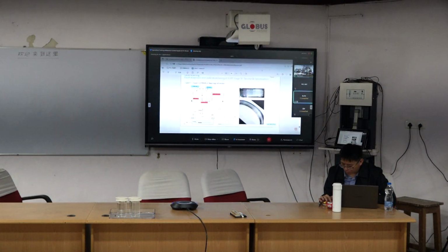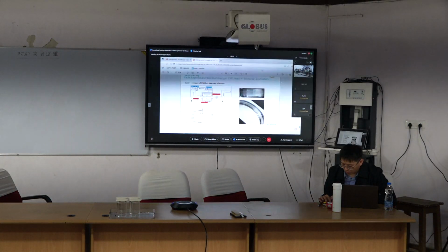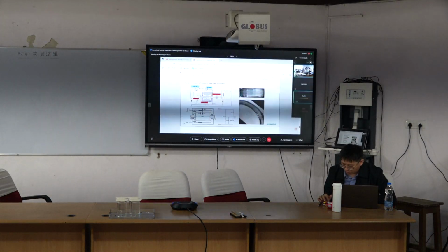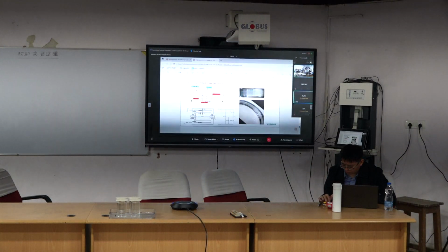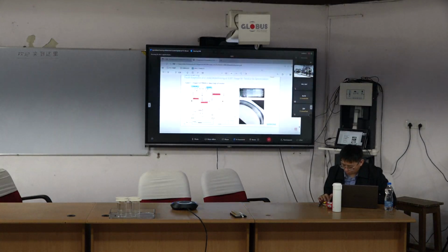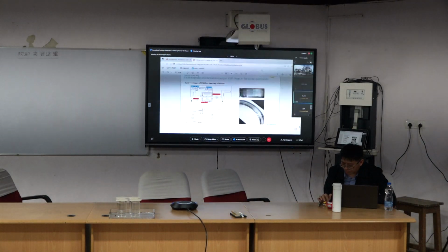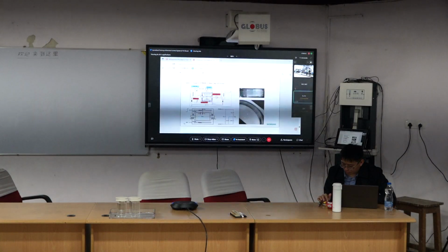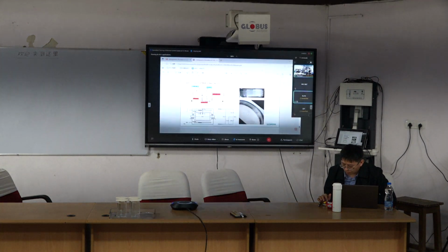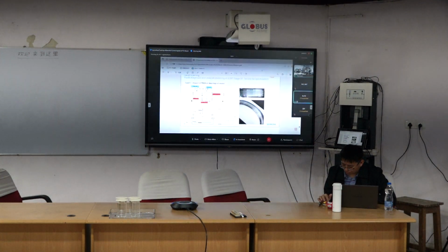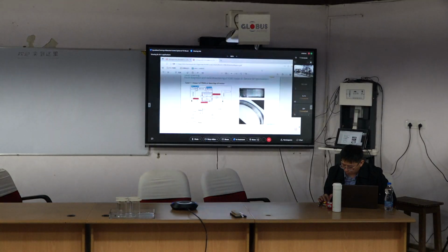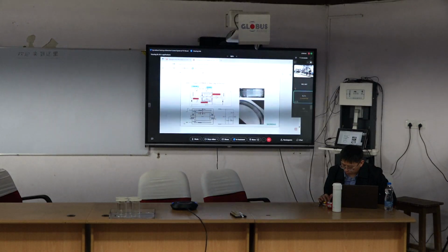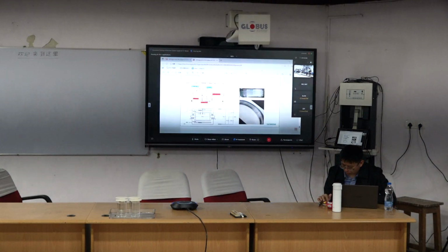It discharges the bearing capacitor CB, where the capacitor CWR is discharging and charging between the winding and the rotor, okay? In the worst case scenario, the bearing voltage can reach such high values that the lubricating film on the bearing breaks down and the capacitors CB and CWR are discharged by a high current pulse. This is the EDM.